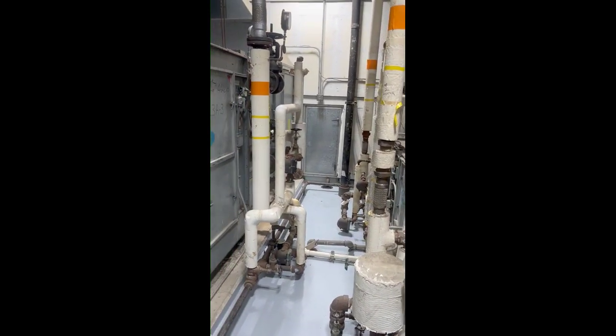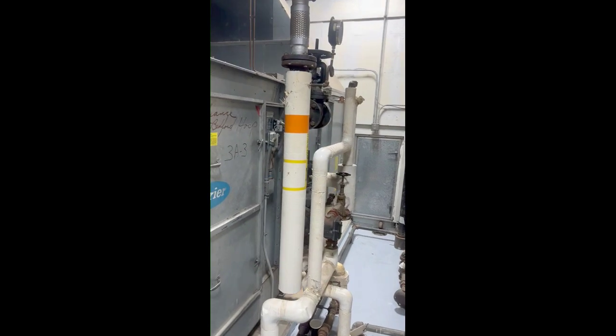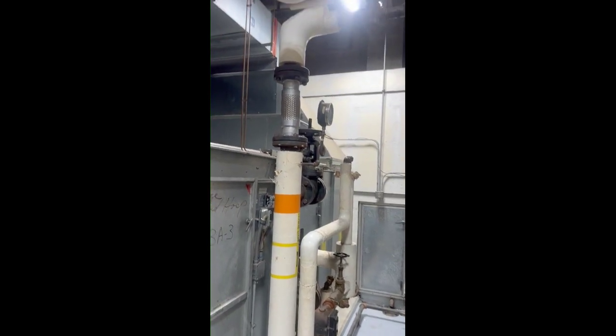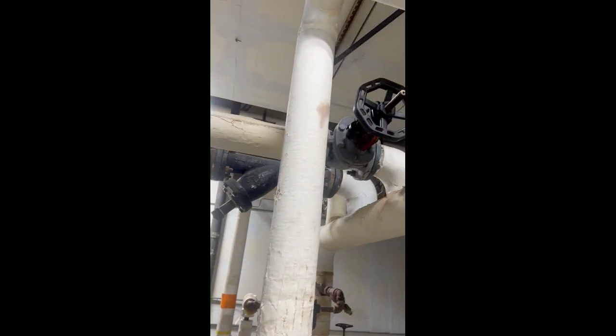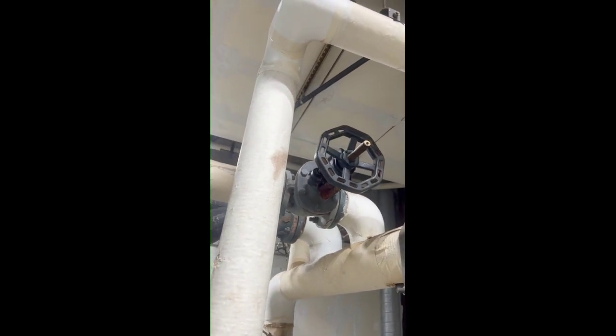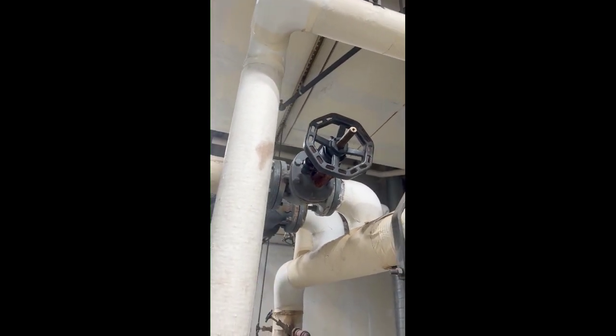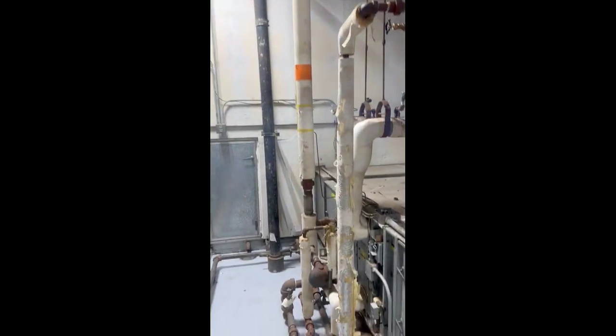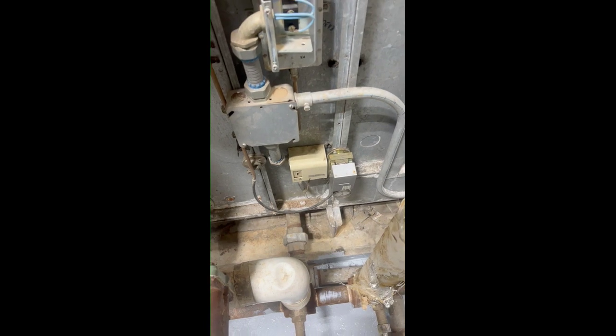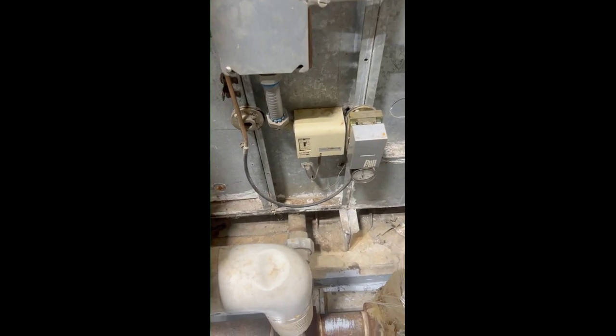So our future series will have different videos talking about pump rebuilding, rod rebuilding. I see a steam leak coming from the packing right there. It's not a major deal, but I want to get that fixed. And this unit right here, air handler 1, is not running. I'm going to come down here and I think it's the old fuse stuff. I could tell this unit wasn't running because it was too quiet.